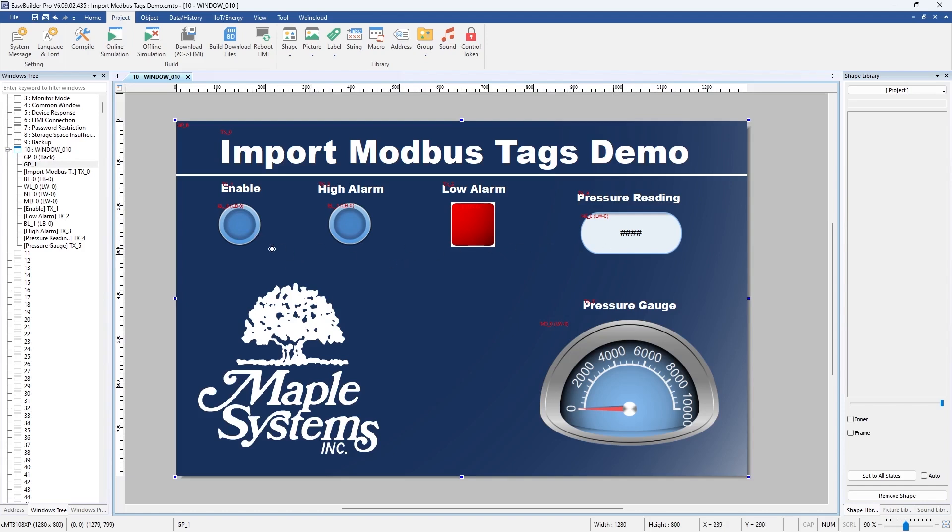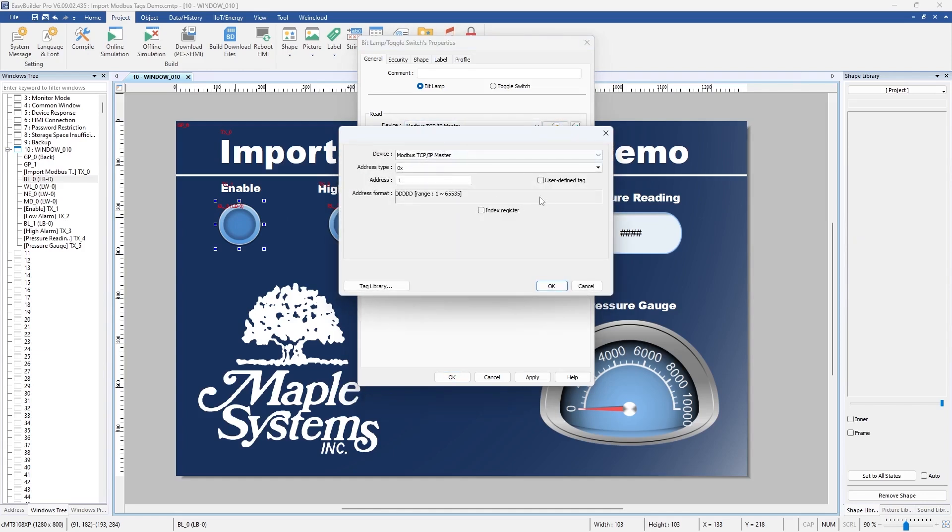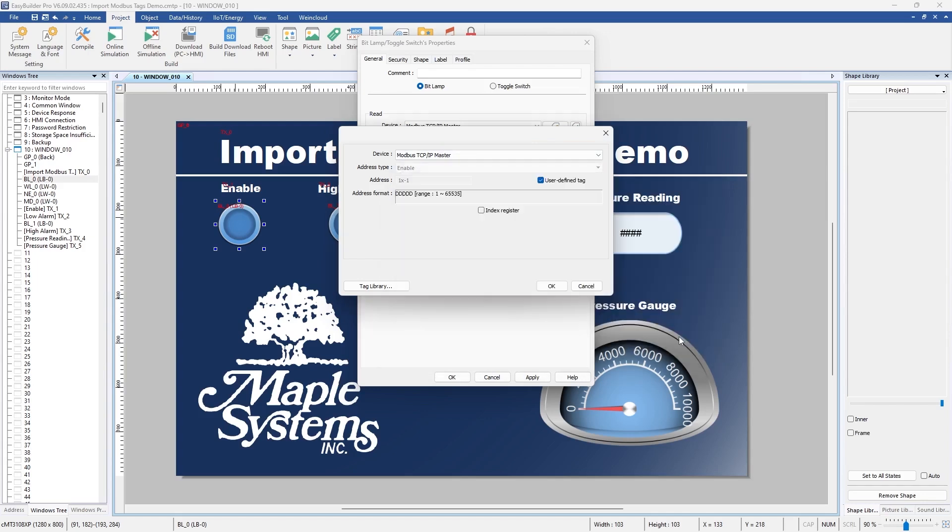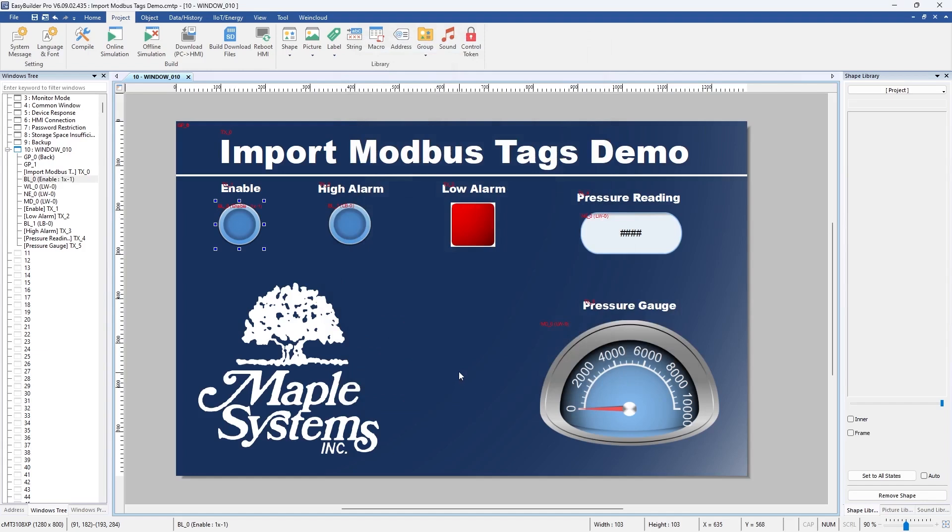So first I'll take this enable button here and I'll double click on the object and I'll go to Modbus TCP IP master and then I'm going to click the settings button here and check off user defined tag. That's the enable tag that we imported. So we want that one. Click OK. Apply. OK. And I'm going to do that for all the objects in this project.